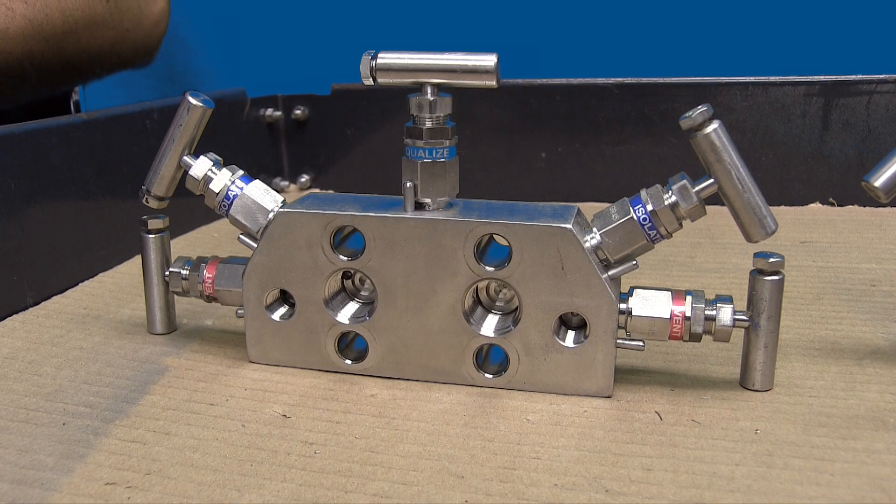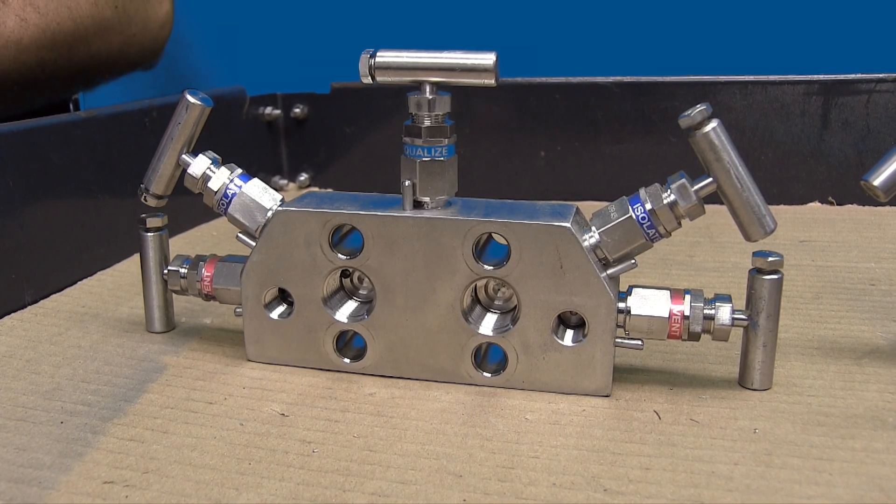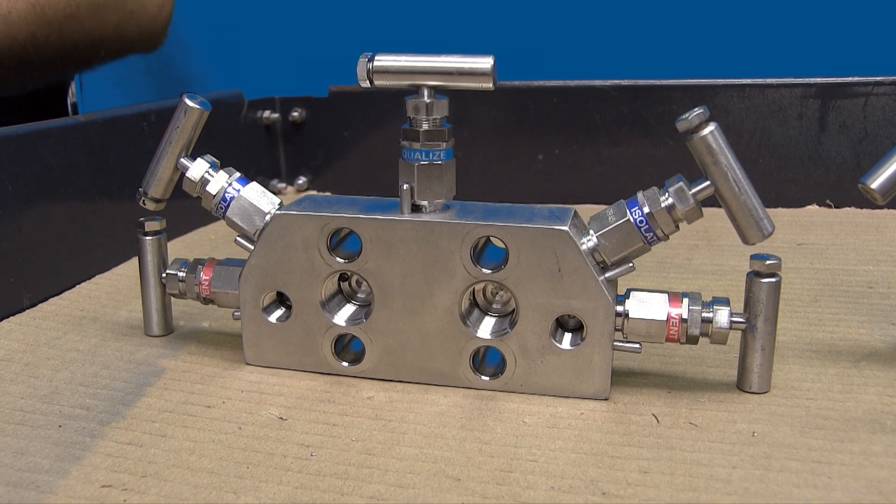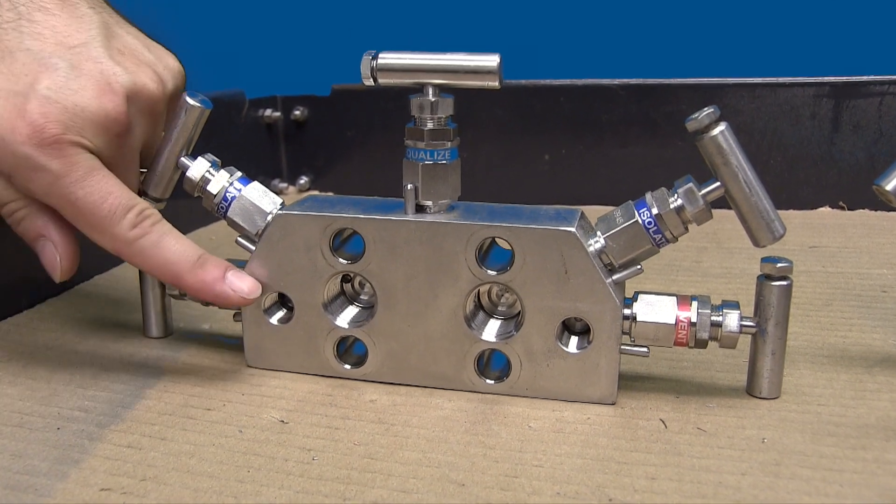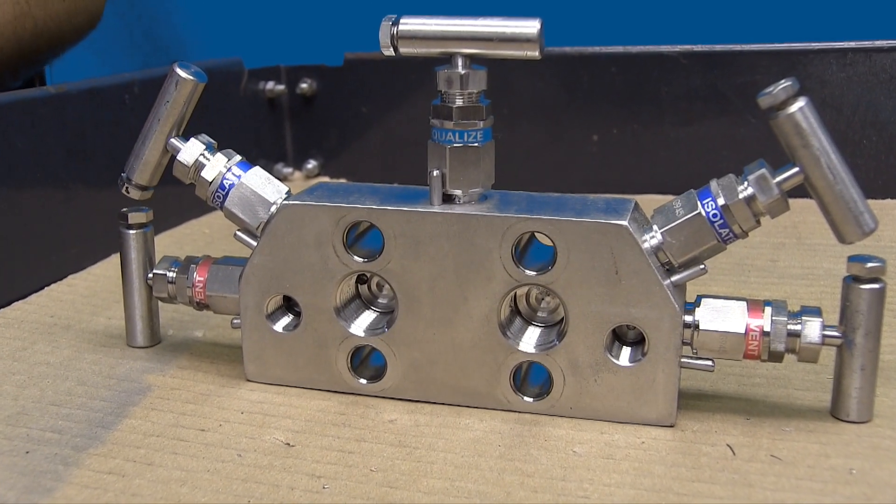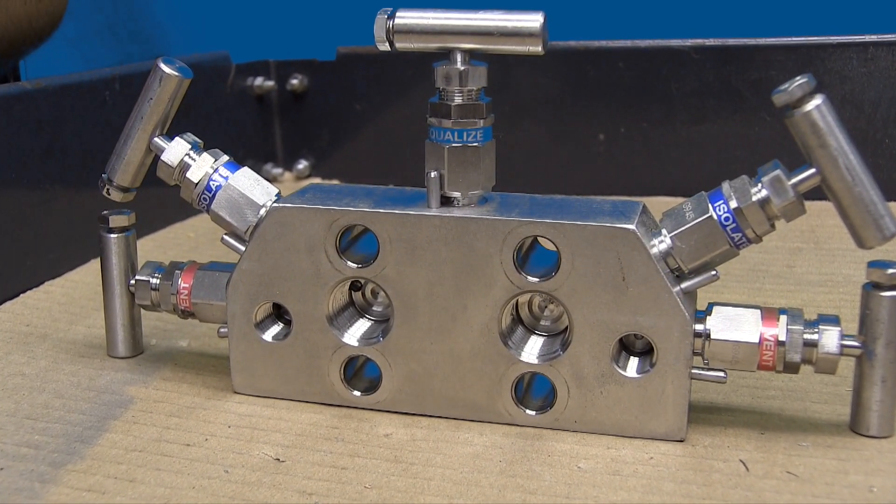Five-valve manifolds are also used on differential setups and provide the ability to block, equalize, and vent two process connections. The five-valve manifold has quarter-inch connections on each process connection that are usually plugged but could be ported out to some other indicator or transmitter for simultaneous operation or measurement.